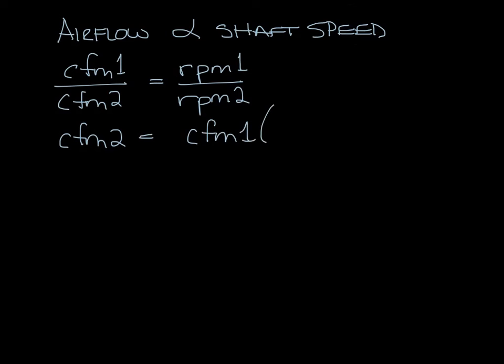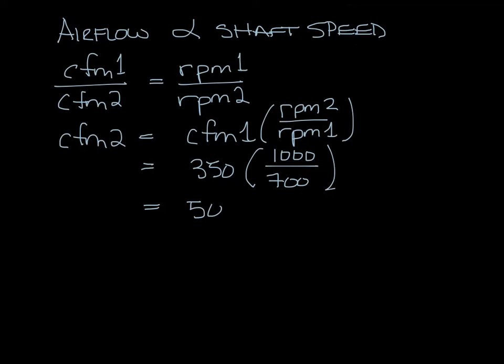So that would be CFM1 times RPM2 divided by RPM1. So let's say we have 350 CFM at 700 RPM and we want to go to 1000 RPM. And that would give us 500 CFM.